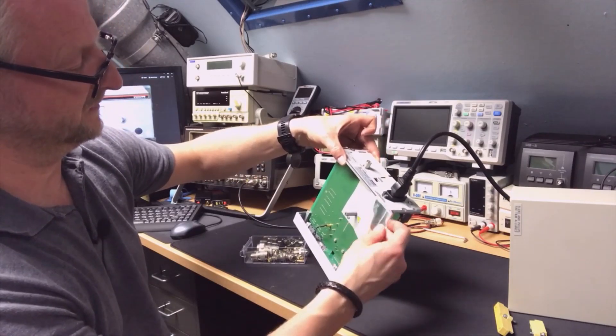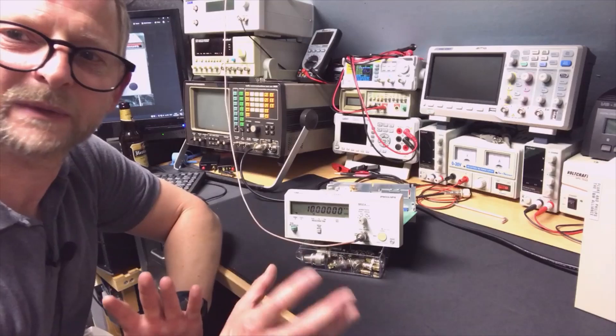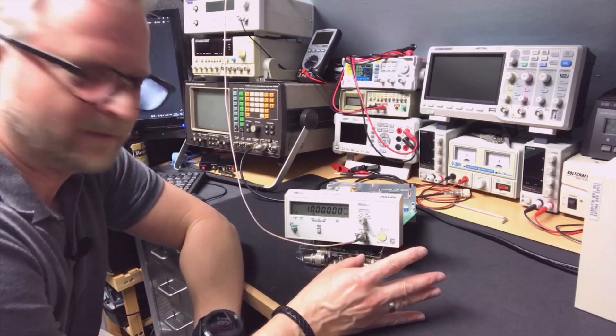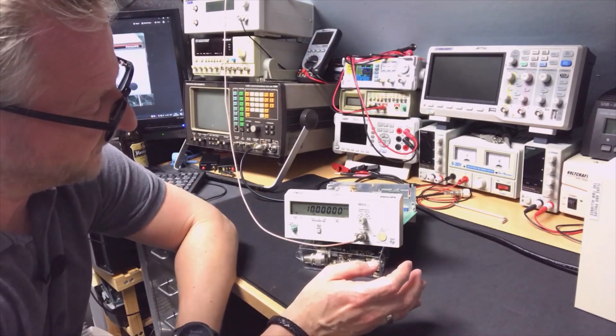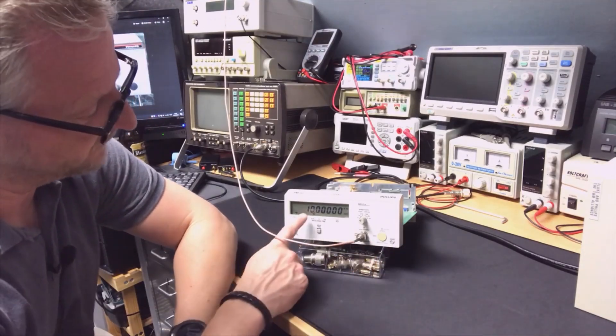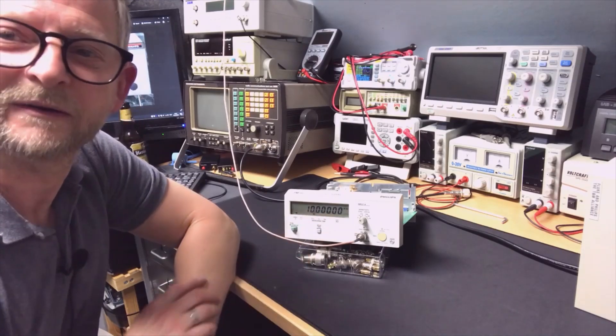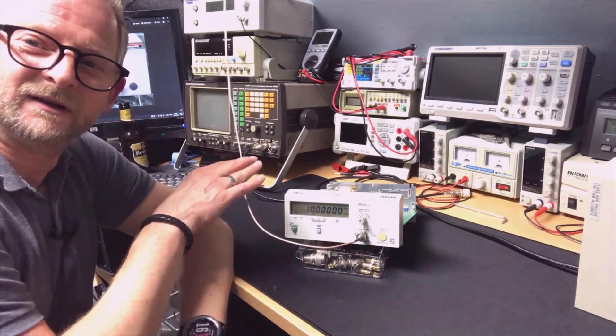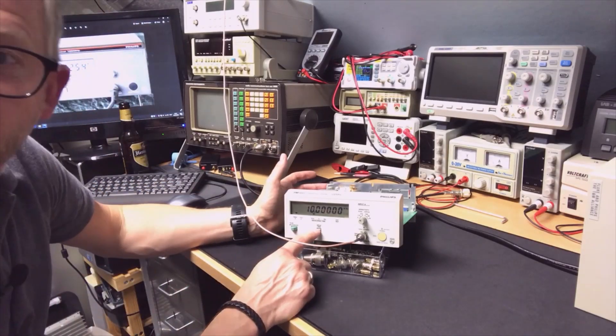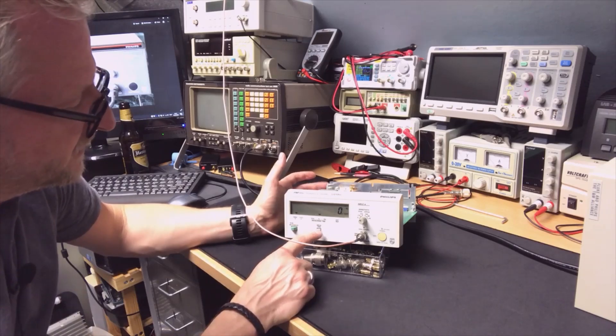It's been on for a while, so it should be warm enough or stabilized. This is on 0.2 seconds, and it says 10.0000. This is on the lab reference, so 10 is 10 here. Let's put it on one second and see what that does.